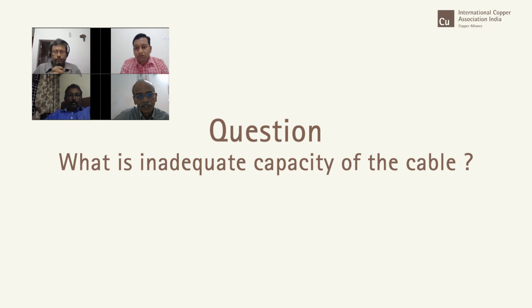Another important thing is, you also know that Mr. Sivaram Krishnan mentioned that the voltage drop across any length of cable, from one end to the other, should not be more than 2 volts. So obviously, if you have current flowing more than that, the cable will get heated up and the resistance also will increase. So for all these reasons, you need to refer to the cable manufacturers' standards, and then go by that.